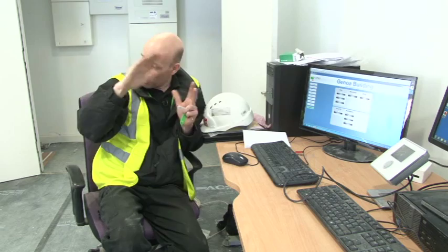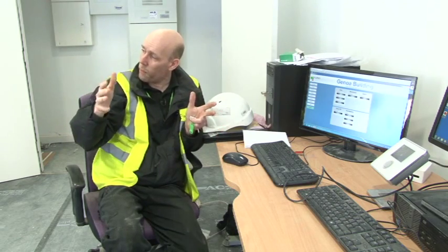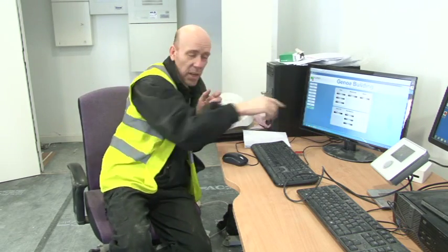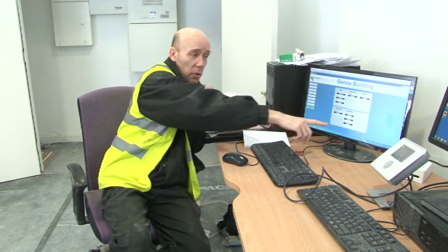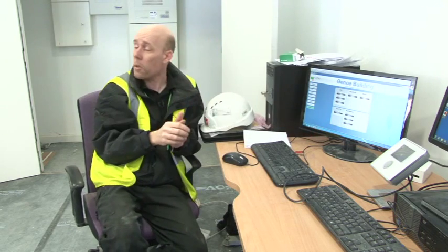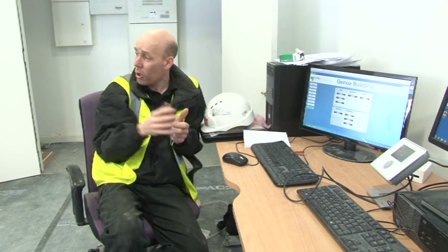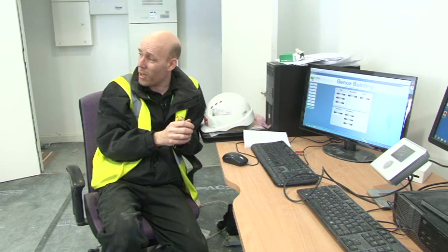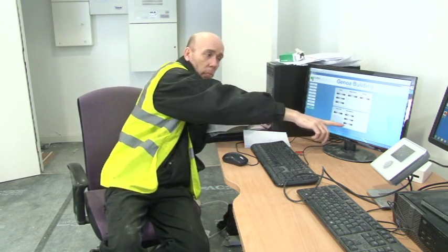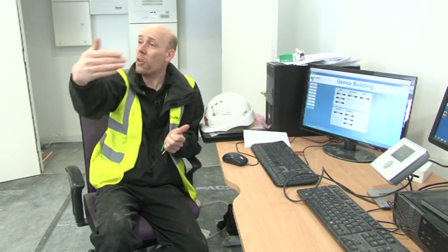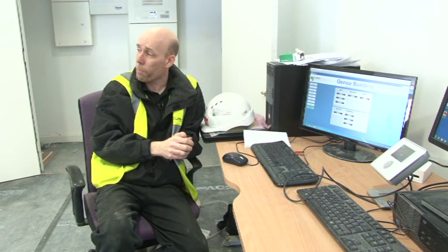So the heat in the system is 100%. If 40% of it's going to the residential, it'll tell you how much of the heat produced is used by the residential. It tells you how much of the heat is produced by the CHP and how much is used by ASDA's retail department. So if you need to charge the heat generation to ASDA, because you're in charge of the heat generation with the boiler, plant room, etc., that one's the number that you're exporting heat to ASDA's plant room. And that's where you can get your reading from should you need to.